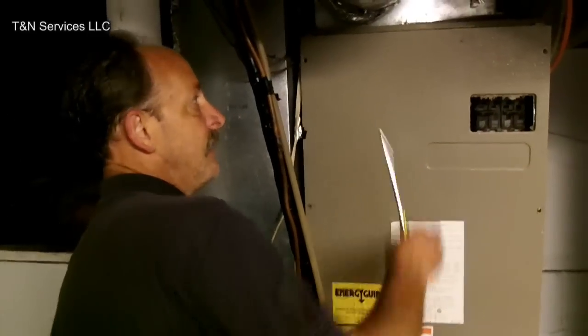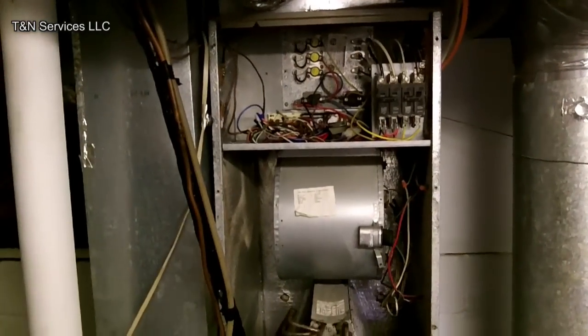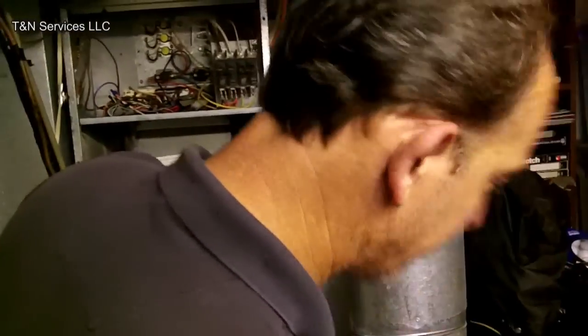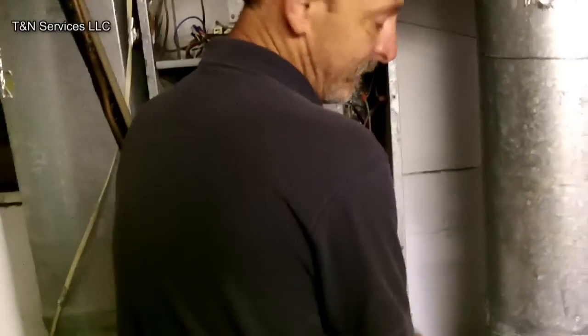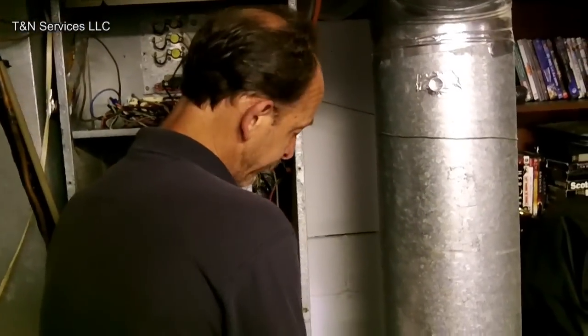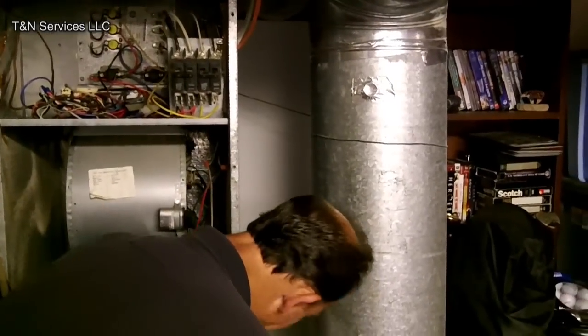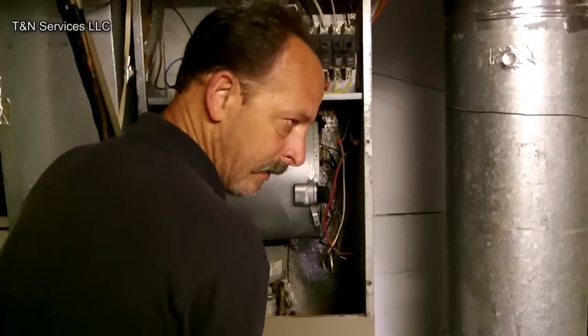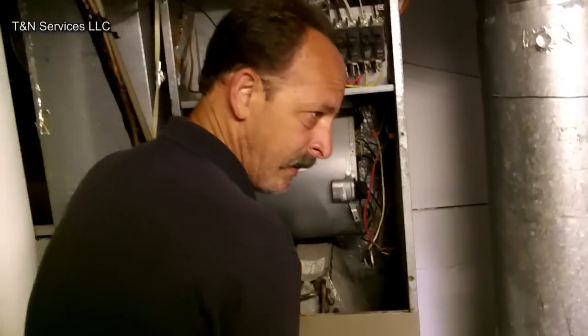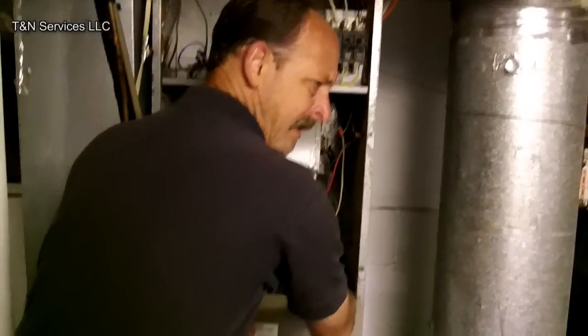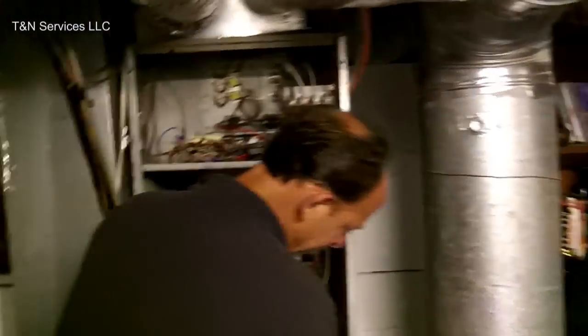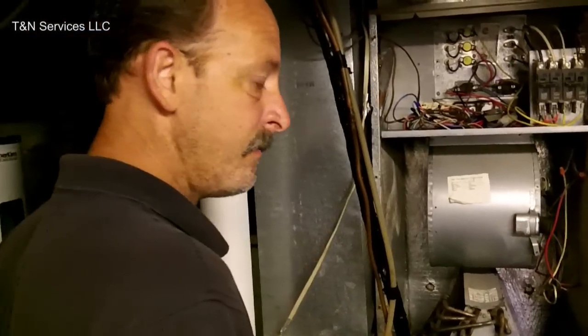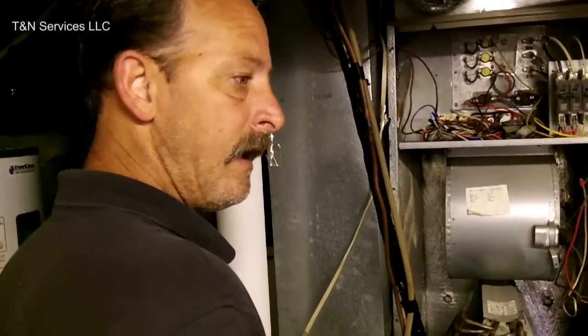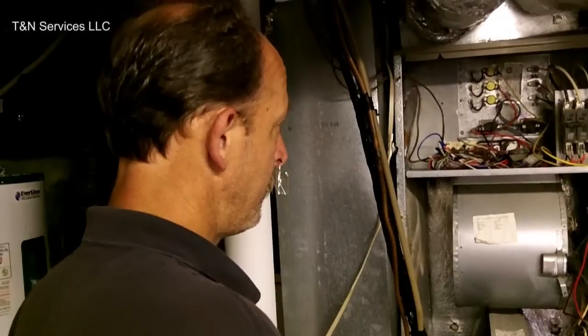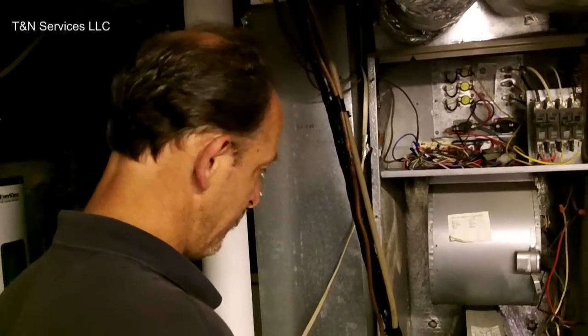Now, like I said, I did do a leak check on this before I even said anything about cleaning it, because it's a 10-year-old unit, and you know as well as I do, with a 10-year-old unit, the chance of having a leak is pretty great. When I checked the Freon last night, I had a 79 pound suction and a 187 head, and if you don't check superheat, the pressures would have looked fine and the house would never cool. So today we should be okay after we get this thing cleaned.